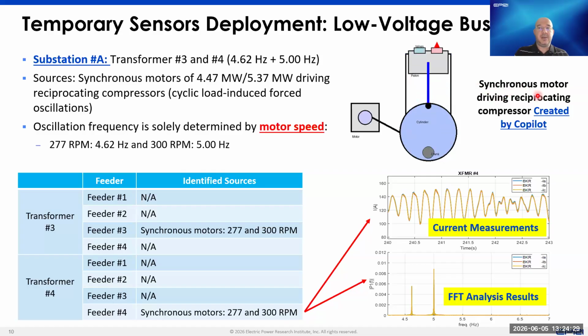And these are synchronous motors that are driving reciprocating compressors. So again, these are motors that are used for industrial processes, and they have a cyclic load pattern. The very interesting thing was that, as expected based on the physics, the frequency of the oscillations is related to the motor speed. For example, the motors that have a synchronous speed of 277 RPM, if you do the math, this is what creates the 4.62 hertz oscillations. The motors that have a speed of 300 RPM are creating the 5 hertz oscillations.